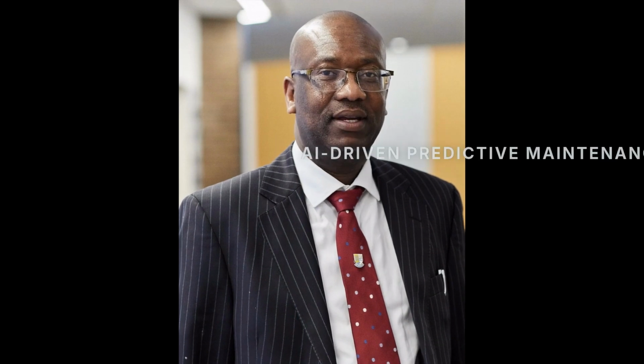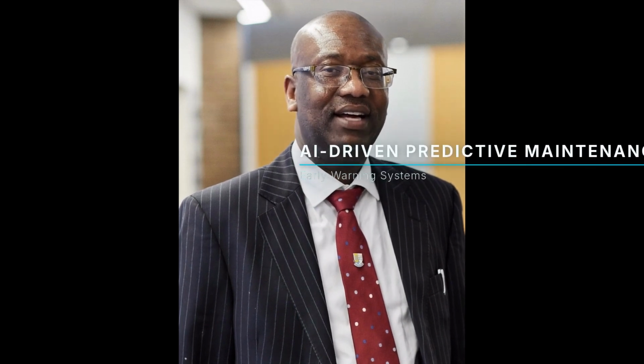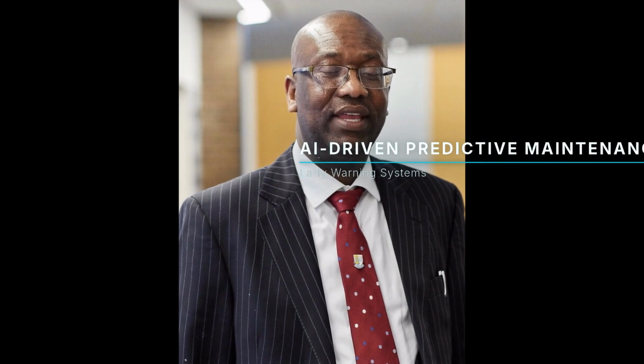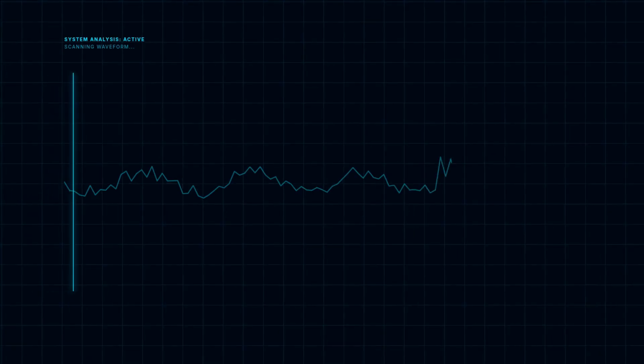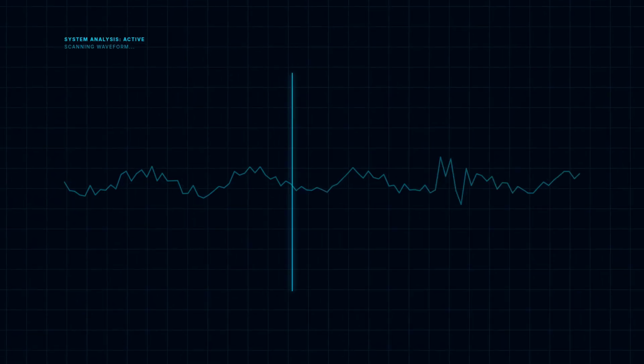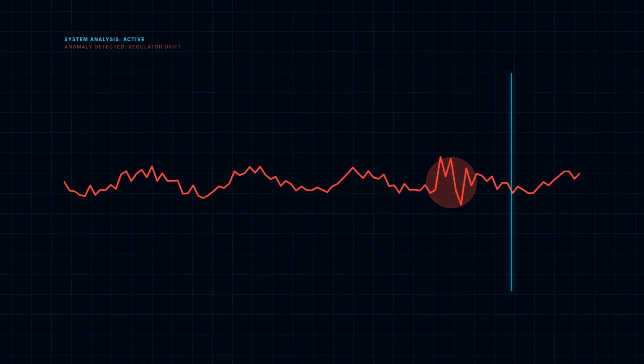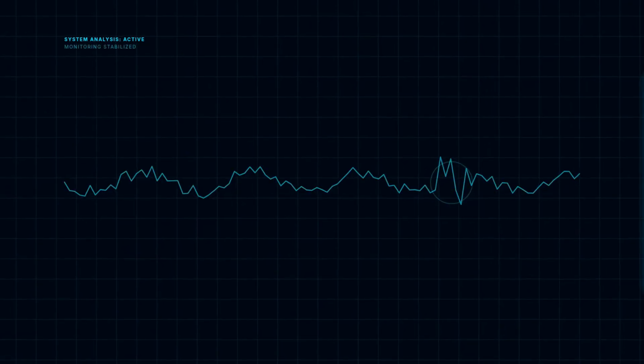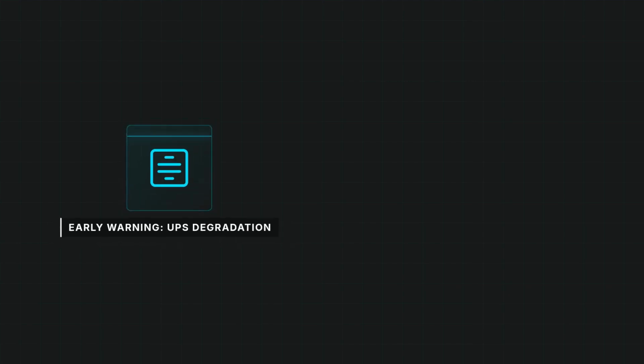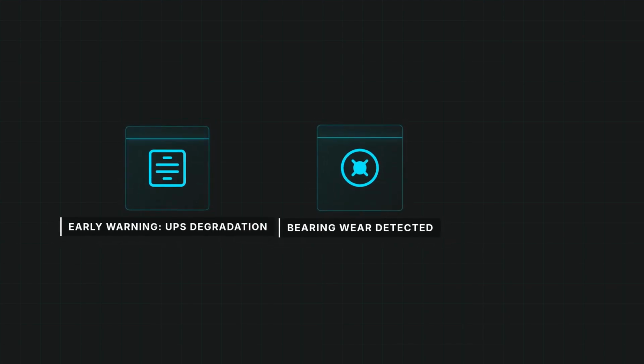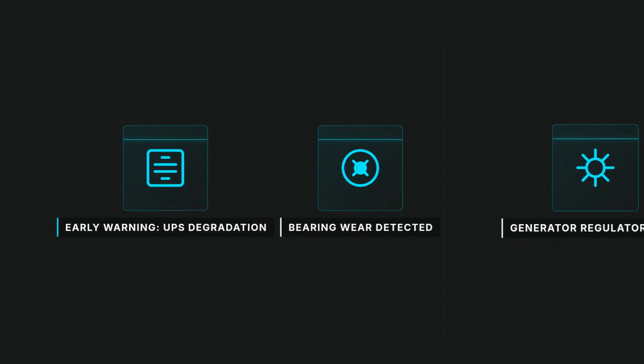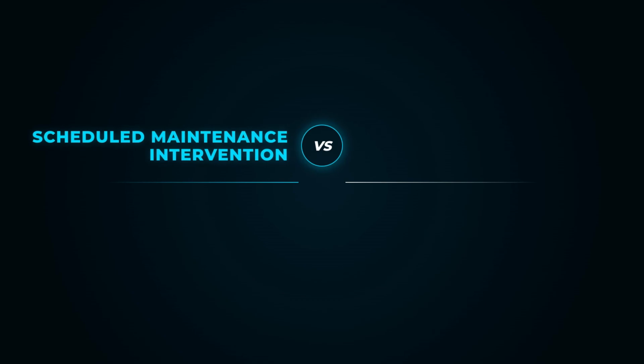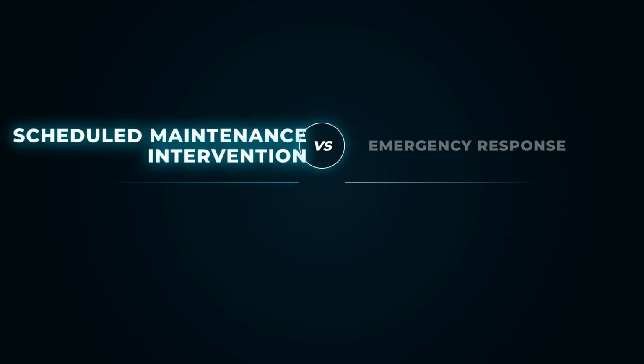The second pillar is predictive maintenance, identifying failures before they even occur. The AI identifies patterns in vibration and power draw that precede equipment failures by 2 to 6 weeks. This includes early warnings for UPS module degradation, cooling pump bearing wear, and generator regulator drift. Early warning allows for scheduled maintenance intervention, completely avoiding the risks of emergency response.